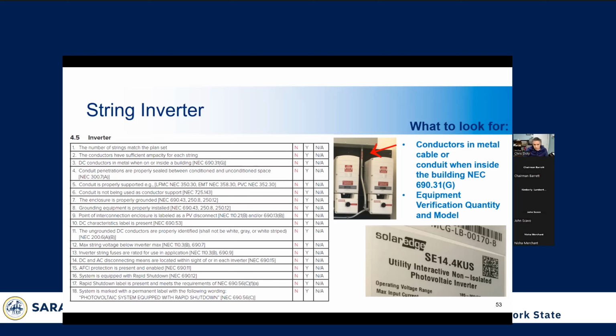So this is typically verified by looking at the inverter nameplate, which is usually on the side or underneath the inverter itself. And in this case, you have DC conductors coming down from the roof. And you can see this label here. Well, you probably can't see it, but we'll show a better example of it later. When you have DC conductors in a metal raceway, you have to label that raceway every 10 feet, showing that it does hold DC wiring. And that's in case of an emergency, if there's emergency personnel and they need to know that there could be live DC wiring in that conduit, if they have to do anything with it.